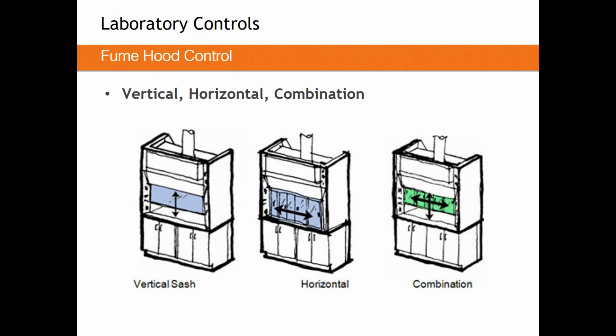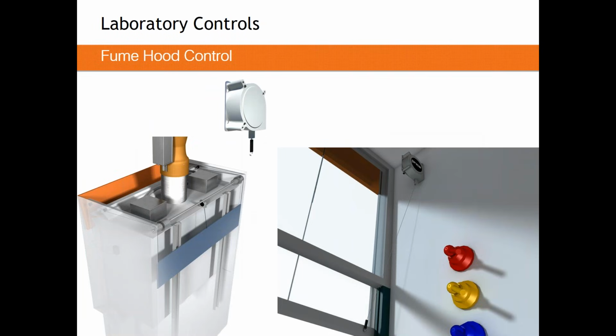Now for all these styles of fume hood, just getting back to the common hoods here, they come in vertical, horizontal, or combination style sashes. In my experience, combination is getting a bit more popular when we look at these hoods. But there are a few types of control we can use for all of these different types of hoods. By far and away, the most common is vertical sash sensing. Vertical sash hoods are still the most common one we see.